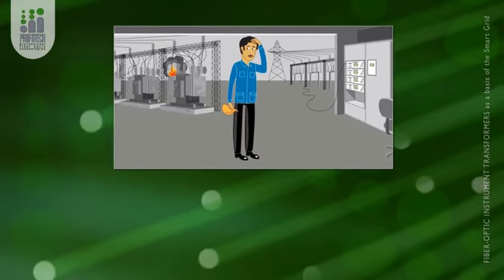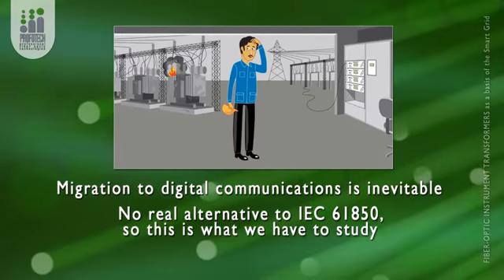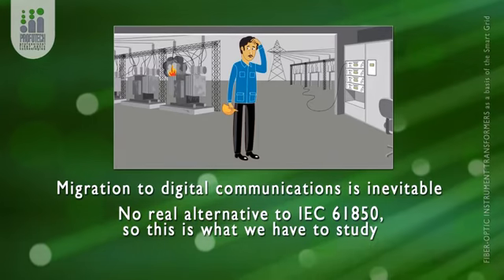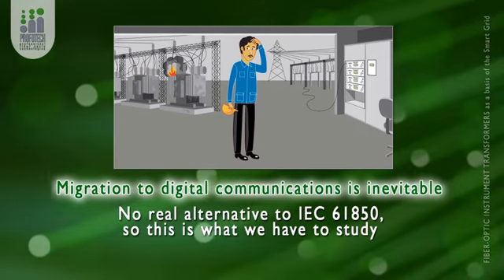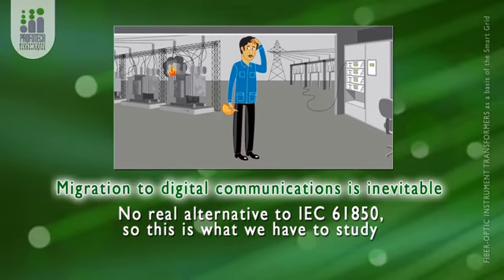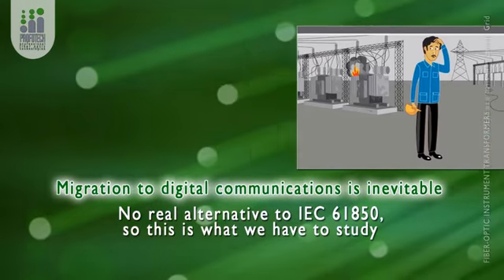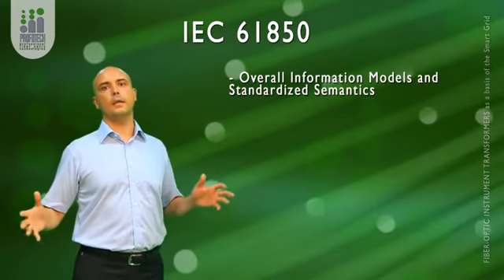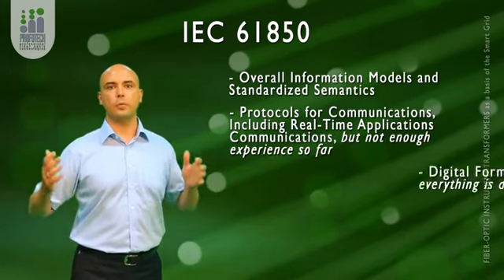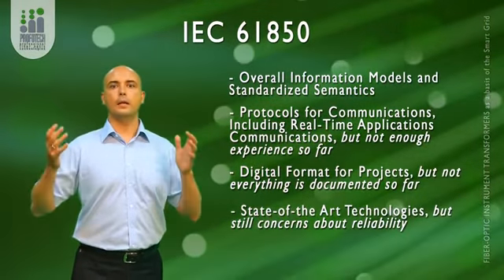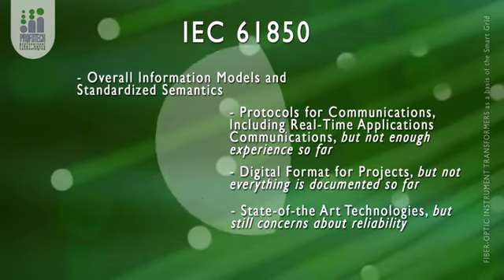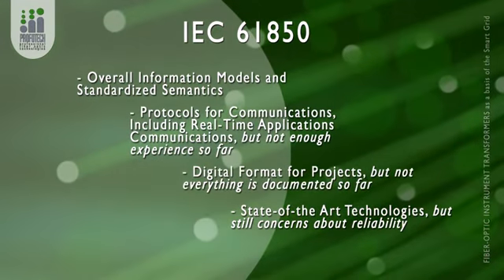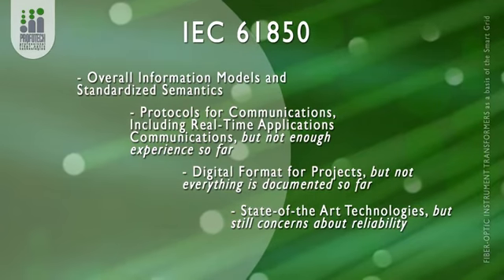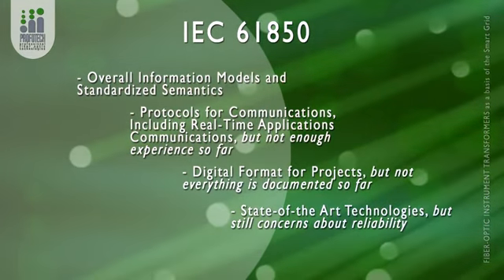All of you probably know about the IEC 61850 standard as being the main standard for digital communication in power energy. And that migration to digital communication in power energy is inevitable. So, it is very hard for me to imagine that we will not transfer our secondary systems to digital communication in the near future. Another point is there is no real alternative to IEC 61850, and that is why the protocols described by this standard include real-time application communication. For example, the protocol that allows us to transfer sample values of current and voltage measurements has never been available or used with any other communication standard.